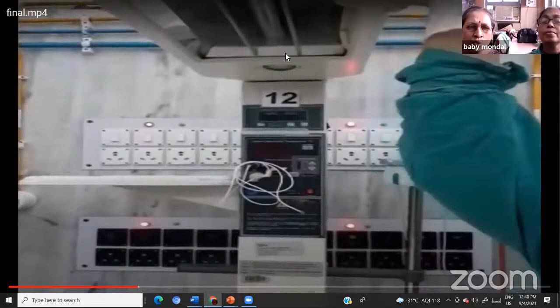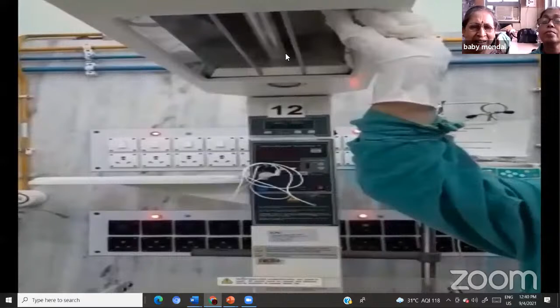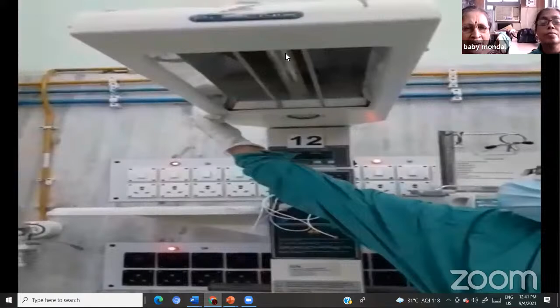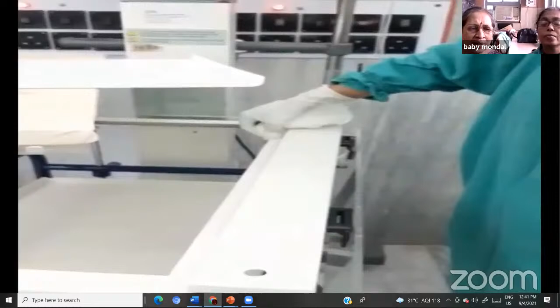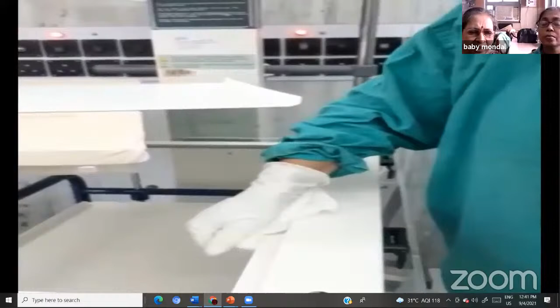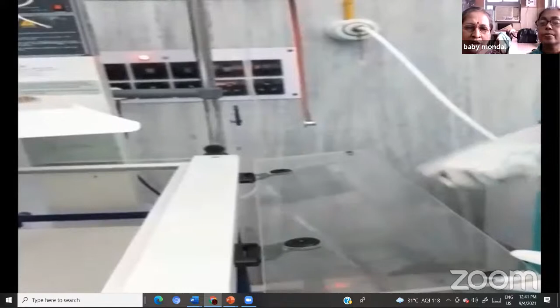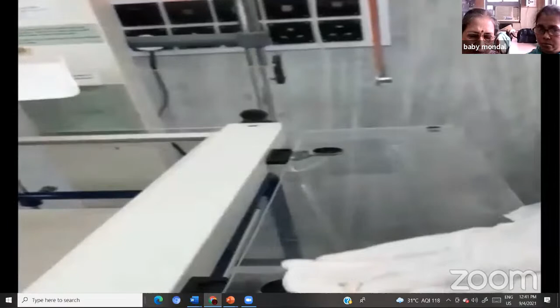Along with the preparation of the radiant warmer, before preparing the bed or bassinet, the radiant warmer was previously demonstrated, so it was cut and added. All the parts of the radiant warmer, including the parabolic reflector and all the rods, are cleaned with 2% bacillocid, considering all the corners, because any dust can spread over the baby and spread microorganisms. In the bassinet, all layers should be removed and all corners disinfected with Bacillol 25. The body of the radiant warmer is disinfected with 2% bacillocid.